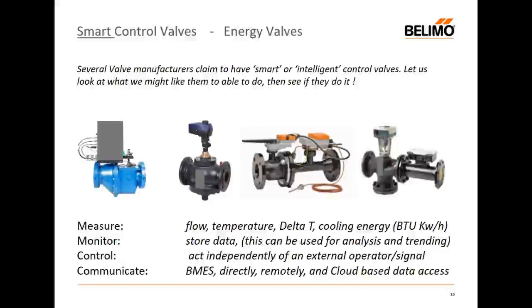Let's look at some smart control valves. There are four here, which I've just taken. There are two here, which are using calculated values for their intelligence. They're using the old mechanical means to determine flow. And the two on this side of the slide are measuring. So I think a measured value is going to beat a calculated value hands down every day, but these are all considered smart valves. Smart because they measure, some calculate, flow, temperature, delta, cooling energy.